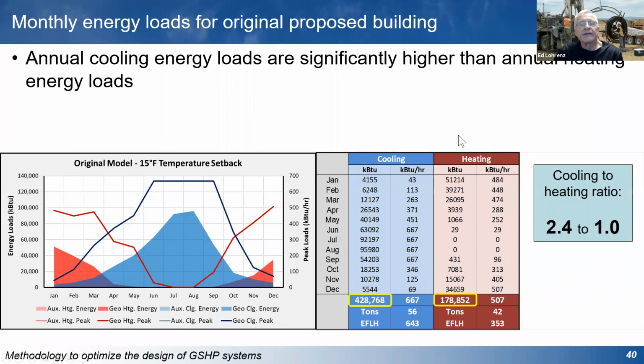So if we look at what the initial loads were for that building, the way the building was proposed, we've got the peak cooling load of about 56 tons, 667,000 BTUs per hour. Heating load is 507,000. The important thing here are these two numbers: 428,000 kBTUs annually that we're trying to reject to the ground versus extracting about 178,000. So that ratio is about 2.4 to 1. A lot more heat rejected to the ground annually than is being extracted from the ground, the way the original building was designed.